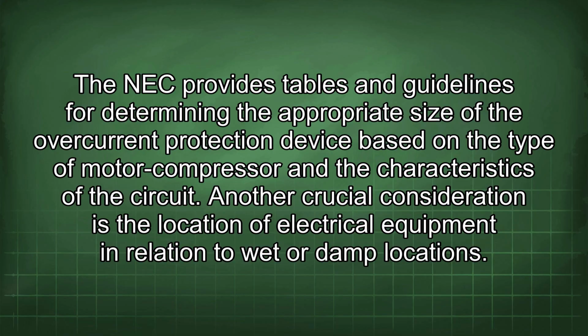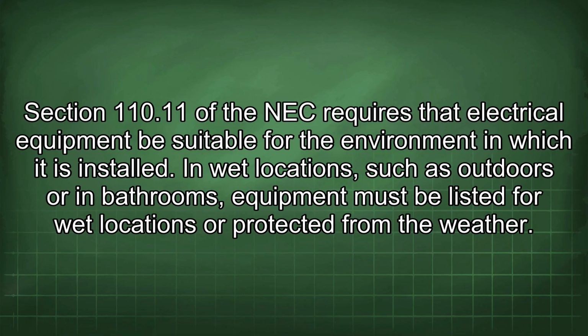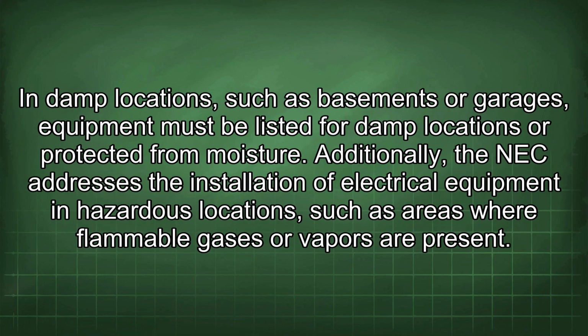Another crucial consideration is the location of electrical equipment in relation to wet or damp locations. Section 110.11 of the NEC requires that electrical equipment be suitable for the environment in which it is installed. In wet locations, such as outdoors or in bathrooms, equipment must be listed for wet locations or protected from the weather. In damp locations, such as basements or garages, equipment must be listed for damp locations or protected from moisture.